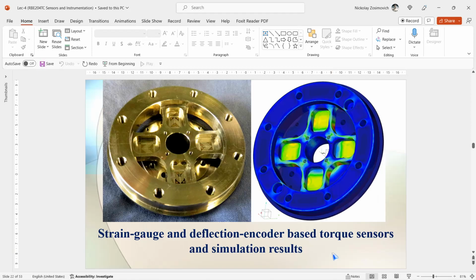Intrinsic shortcomings of strain gauges, like the temperature-dependent sensitivity and nonlinearity, can be reduced by dedicated digital signal processing. Current research is aiming at the development of integrated circuits in which both analog and digital signal processing are combined, resulting in small size, low cost, and versatile interfaces for strain gauges. For example, 4 different algorithms are compared and evaluated, implemented with analog, mixed, and digital hardware, performing gain and offset compensation and correction.